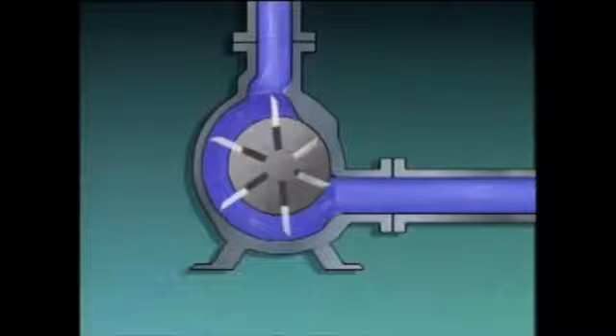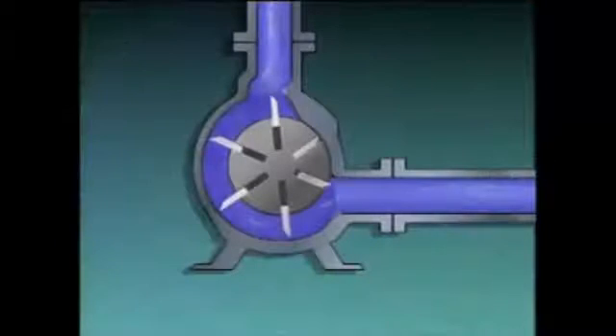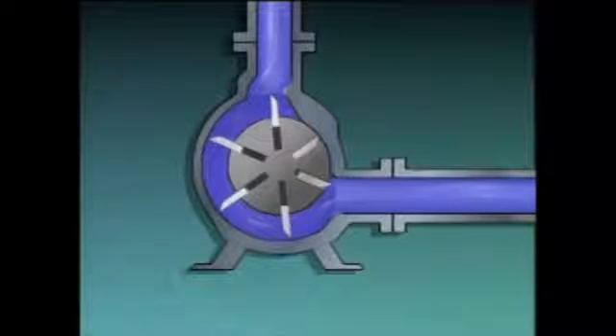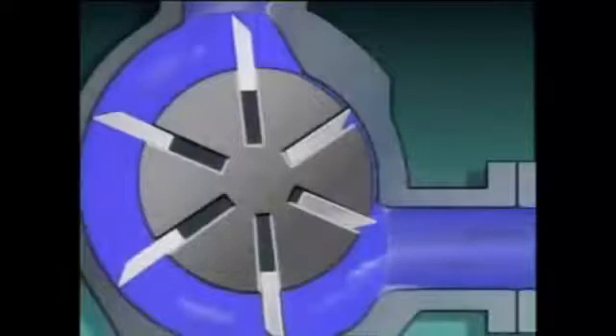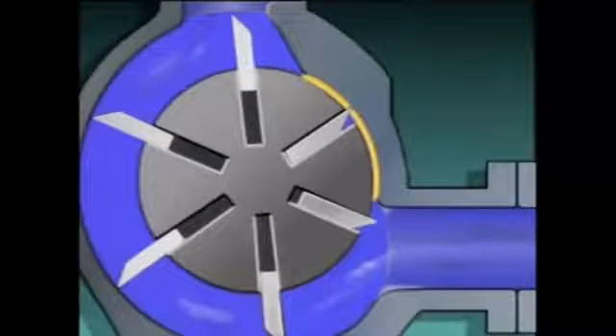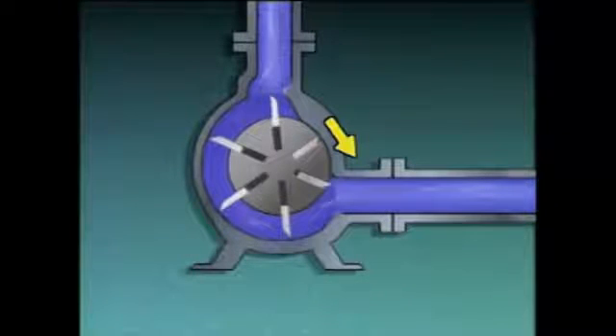At the discharge, the gap between the rotor and the casing becomes very narrow, directing the process liquid out of the pump and forcing the vanes back into the rotor. The reason the gap narrows is because the rotor is offset — positioned away from the center of the casing so that the gap is very narrow where the vanes rotate back to the suction. This narrowing also allows only a small amount of liquid to return to the suction of the pump.